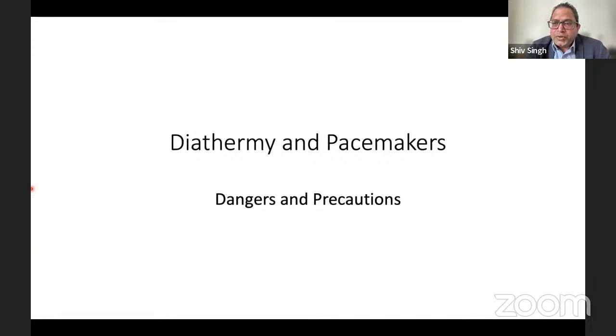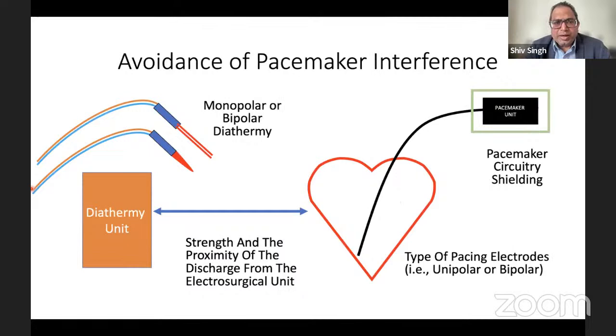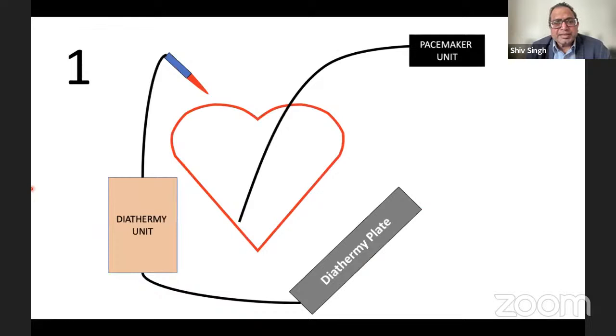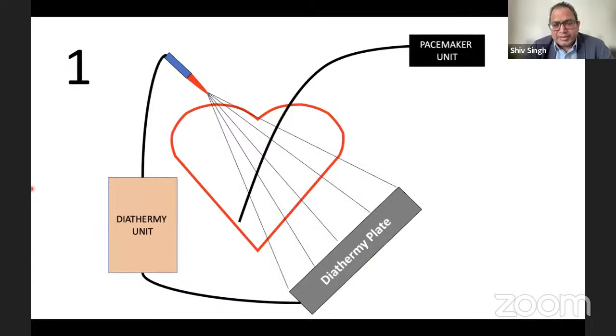One of the other worries about diathermy is pacemakers. What can it do? You want to avoid any pacemaker interference. The pacemaker unit is implanted just below the clavicle and there are wires going in. So it's very important what kind of diathermy you're using, what the strength is, the proximity of the discharge from the diathermy machine, also called the electrosurgical unit, and the types of pacing electrodes. So what can actually go wrong? First, if the current flows through the heart where the wires are, you can have a heating effect, and damage to the sensing electrode.